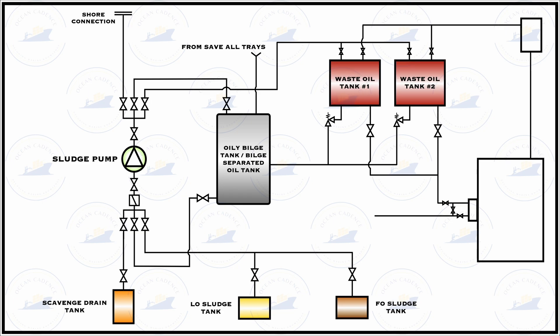The waste oil tank gets filled by the discharge of the sludge pump and has separate arrangements for the evaporation of water present within the sludge, with the help of heating coils available within the waste oil tank. The vent and vapor line allows the water vapor generated by evaporation to go into the funnel section where there is a mist box, and through the mist box to escape into the atmosphere as clean water vapor containing no oil residues.